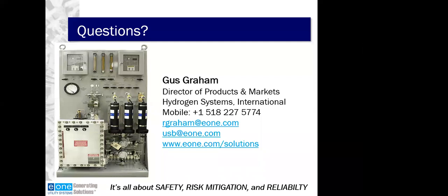Okay, very good. This question comes from Ken. CO2 is used to degas the generator and purge out H2. Can the DHCP also monitor the degas process in terms of H2 being exchanged by CO2? And do DHCPs have temperature compensation for purity accuracy? So a couple different questions there. Very good questions. So the first question about CO2 measurement, yes, that is the fourth measurement location that the DHCP has. And it's typically located on the manifold, the gas manifold area.